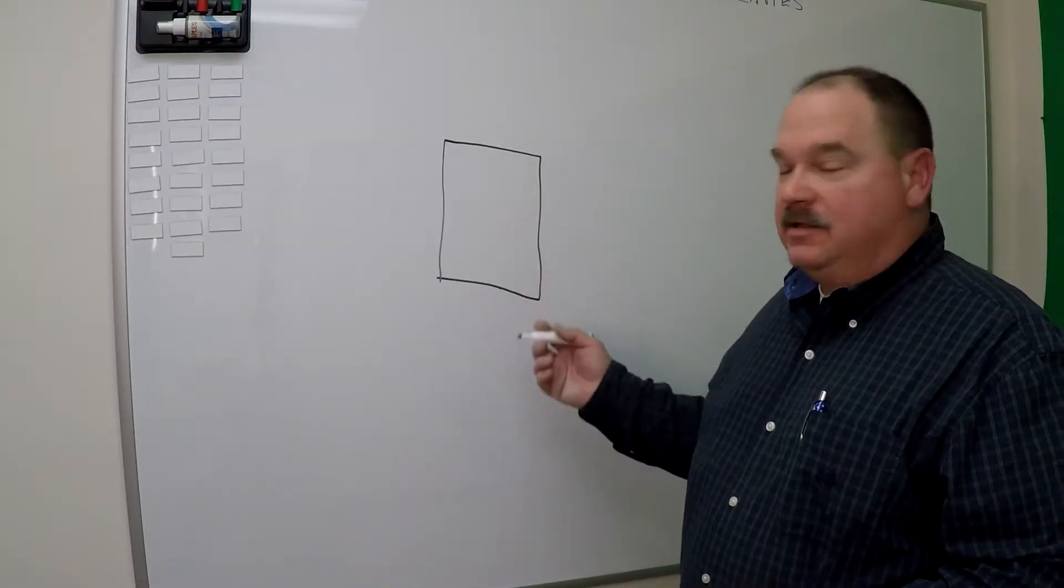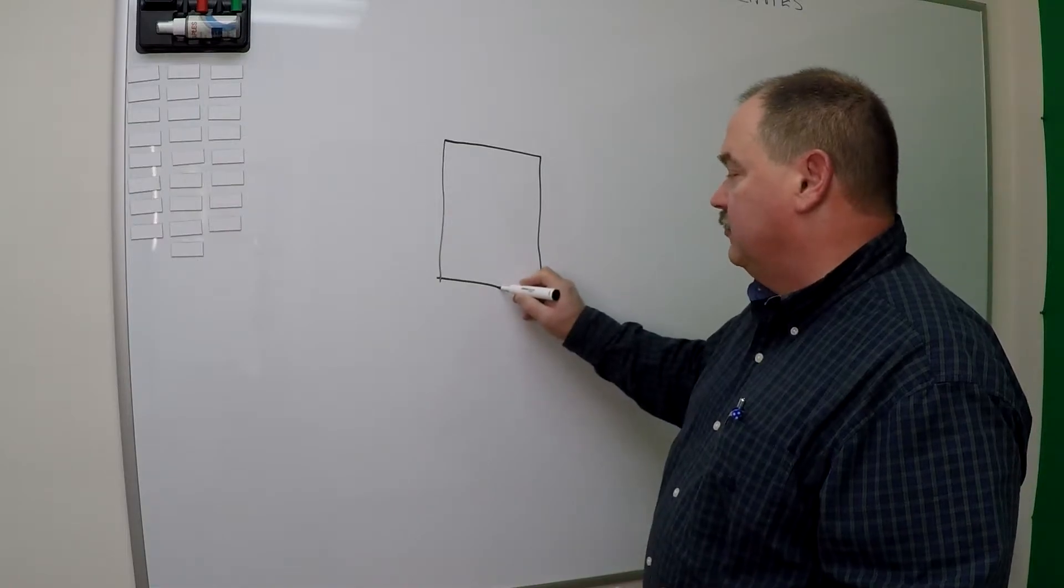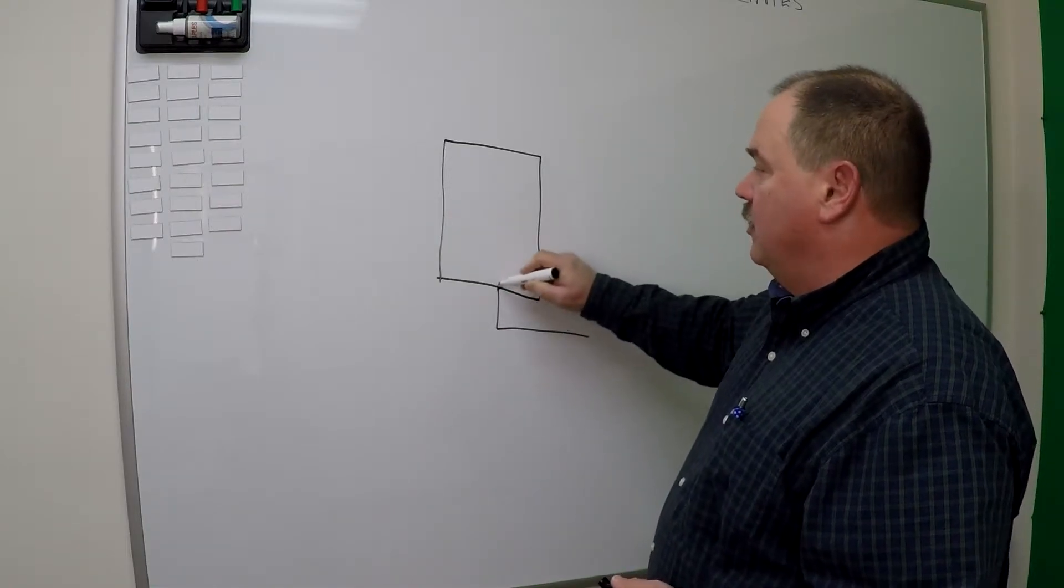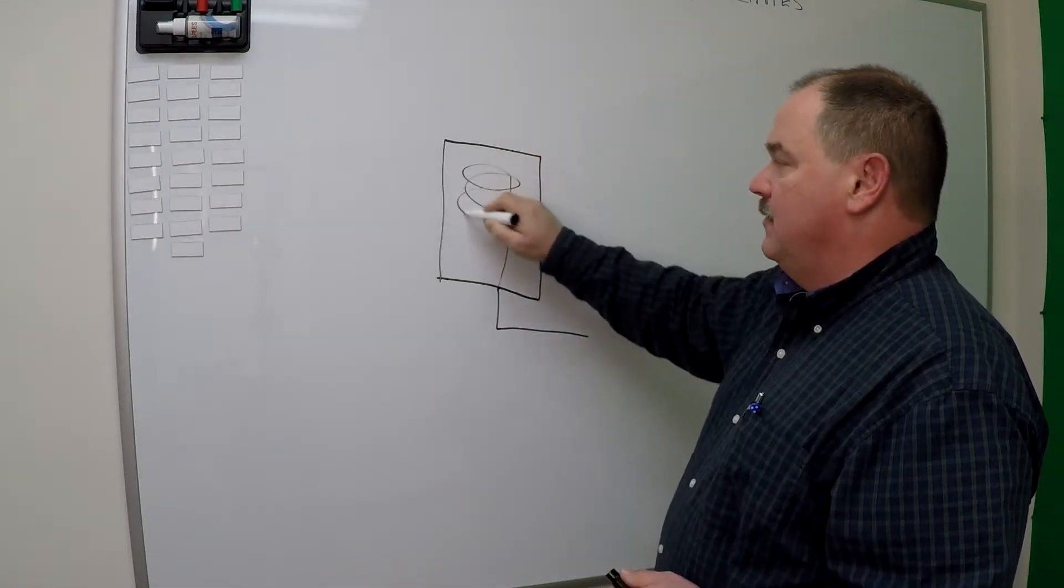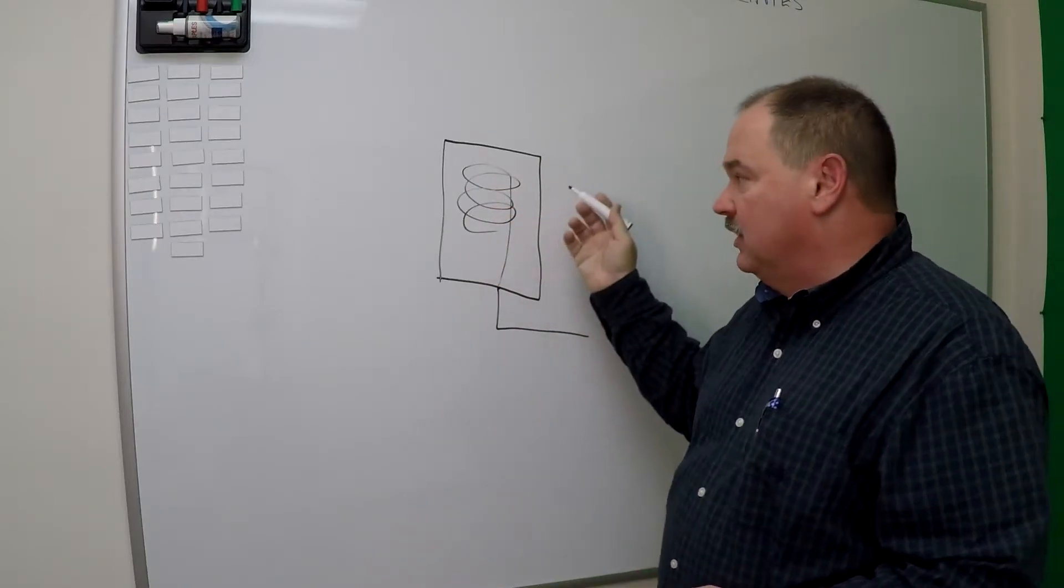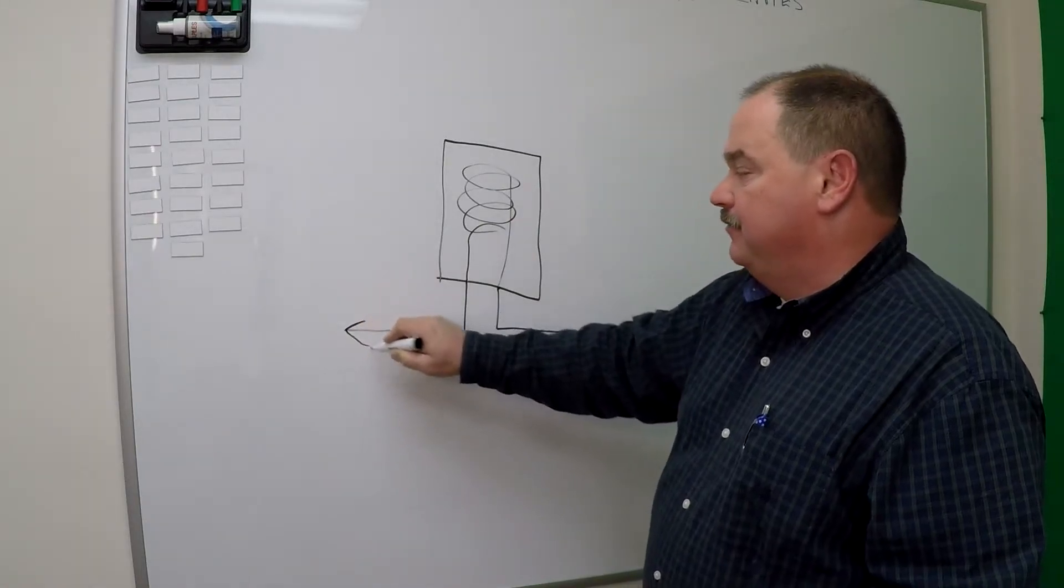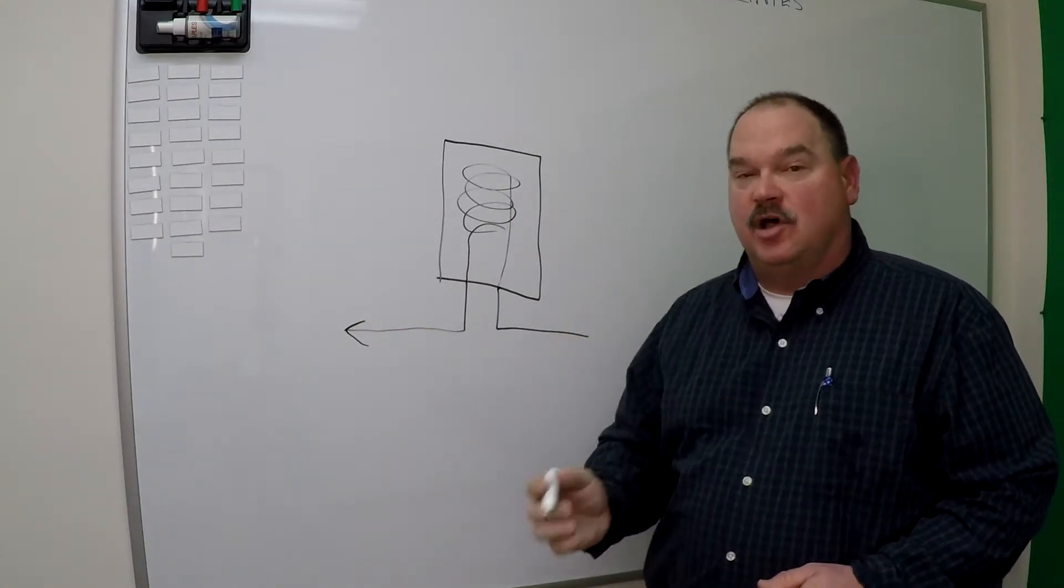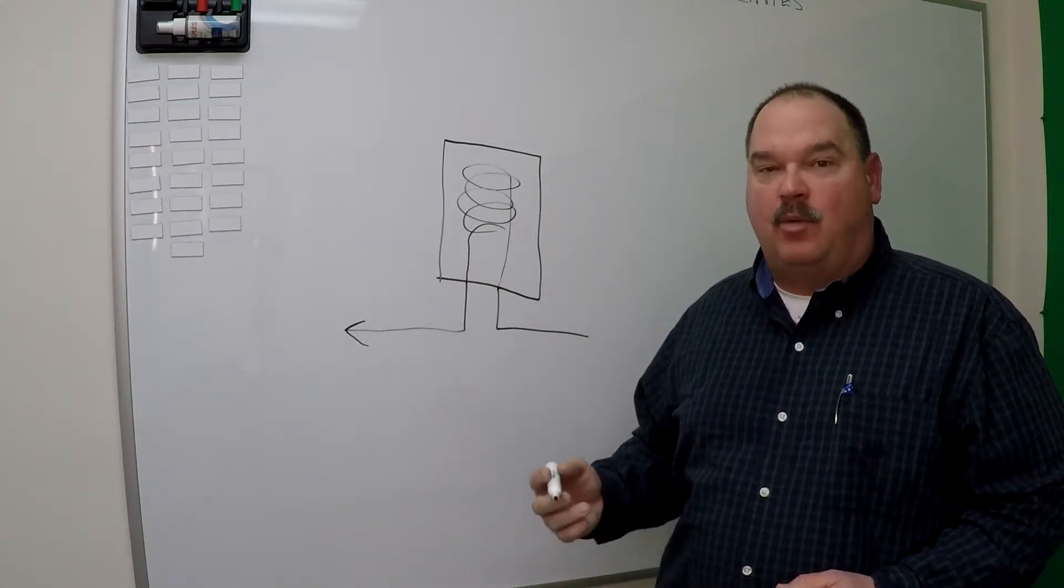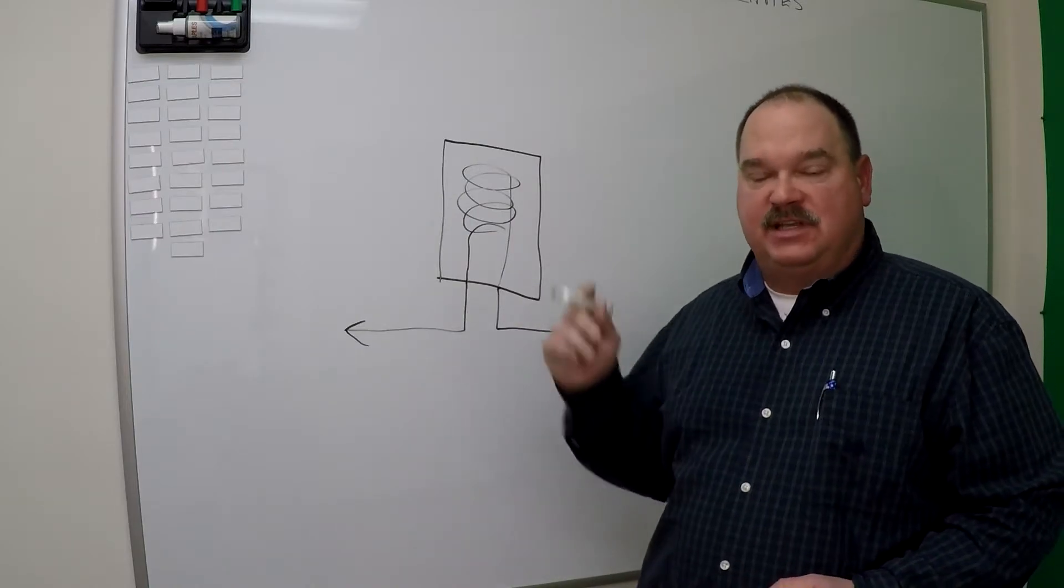In a tankless water heater, and this could be gas or electric, cold water comes in one side, runs through a heat exchanger, and this could be, again, gas or electric, and then out to the house on the hot water side through the pipe. The tankless water heater is always off. It only makes hot water when there's a flow established in the water heater.